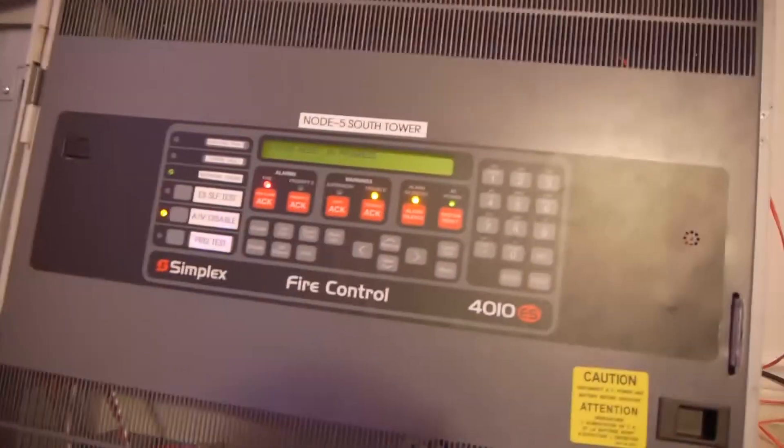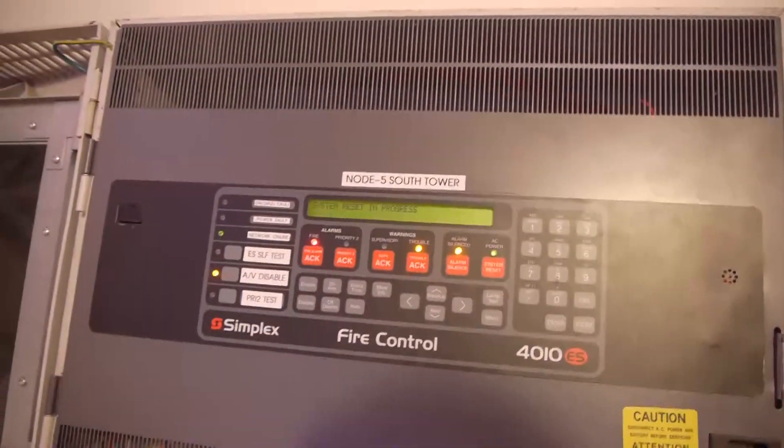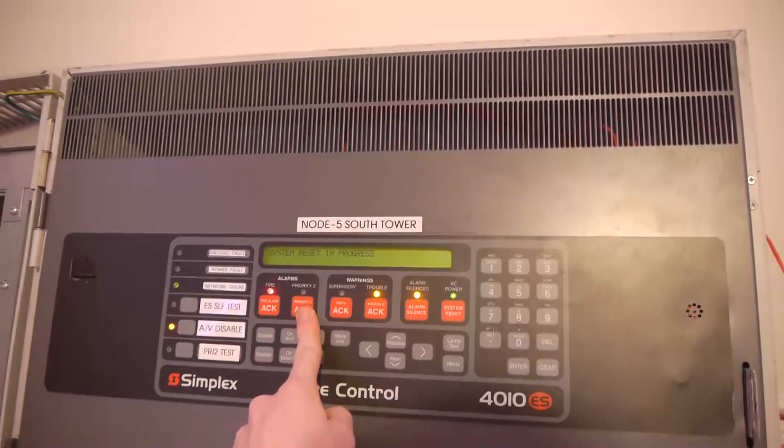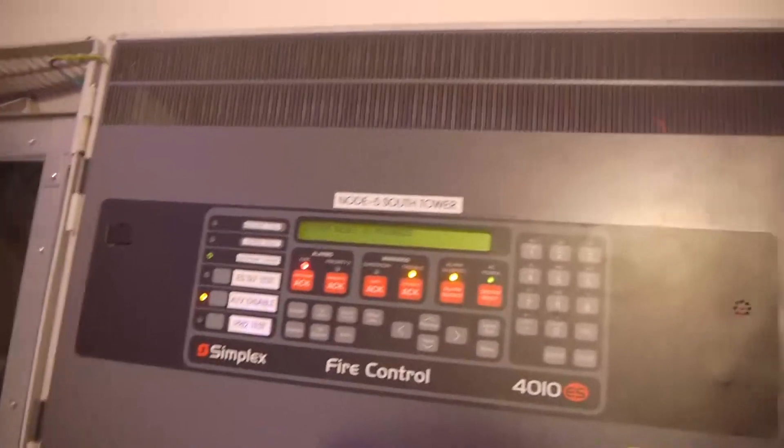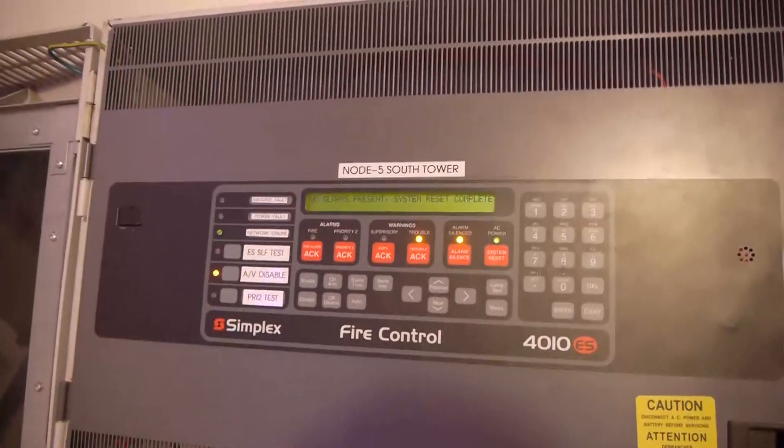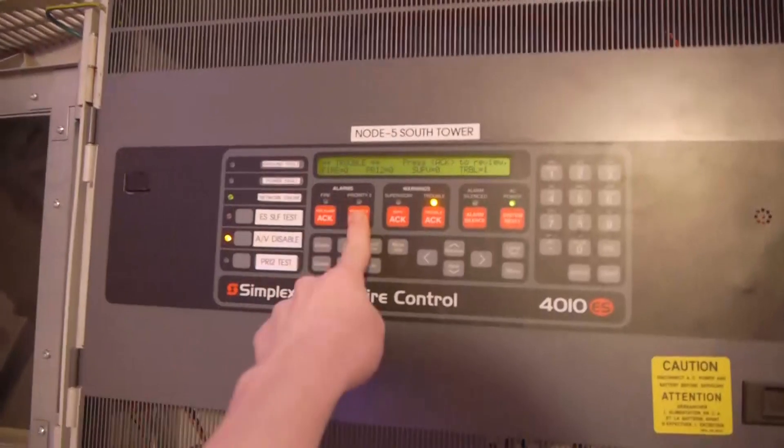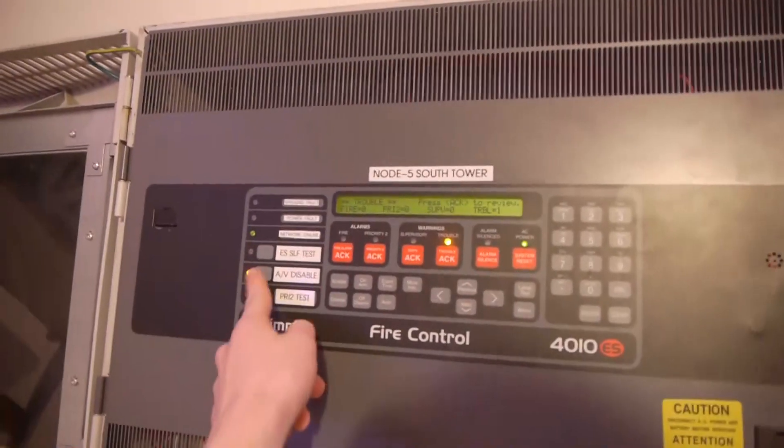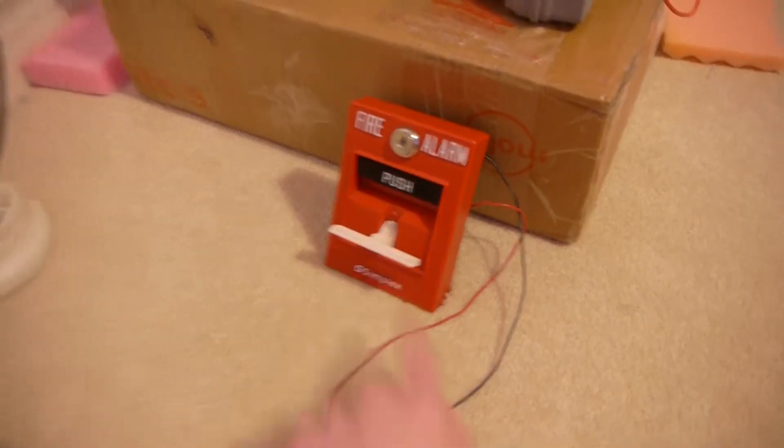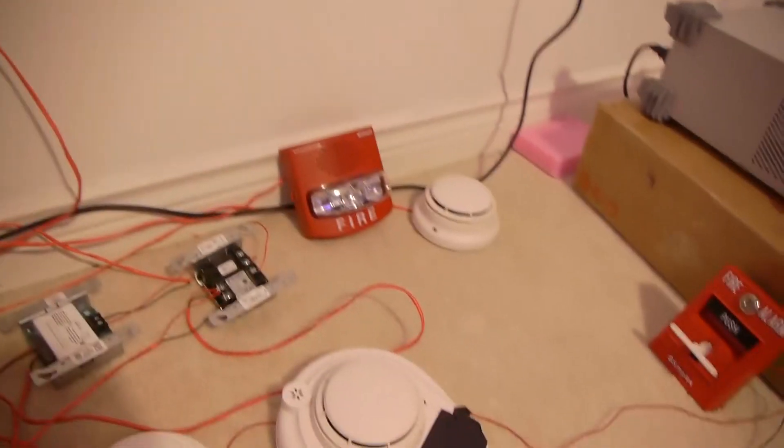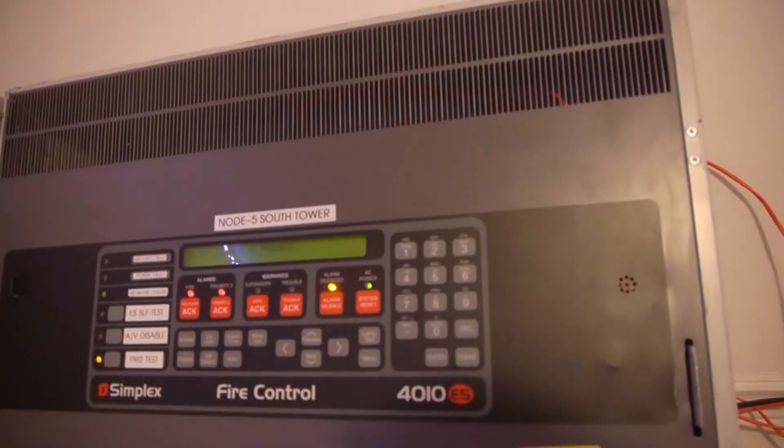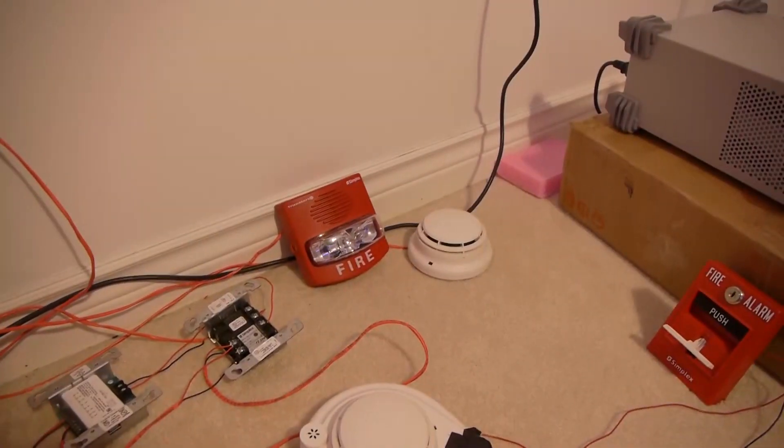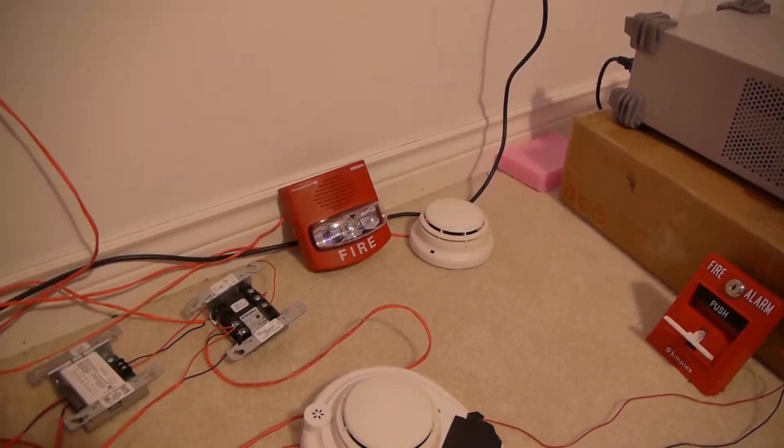And for the final test, I'm going to enable the ES horn strobe, and I'm going to pull the pull station, so you can hear that both of them actually do sync too. Now another thing I will note is carbon monoxide is a lower priority than fire. So what we're going to do in this test is we're going to set off the carbon monoxide, and then we're going to pull the pull station, and we're going to see it switch over from doing carbon monoxide coding over to fire. Because fire is basically priority one, carbon monoxide is priority two, so it's less important than priority one. So we're going to go ahead and re-enable that, and we're going to put it into carbon monoxide mode, and now we're going to go ahead and activate the pull station. Now you can hear that syncing. It takes a second for the ES device to turn off, and as you can hear it switched over to doing code three, which is all the custom programming I did.